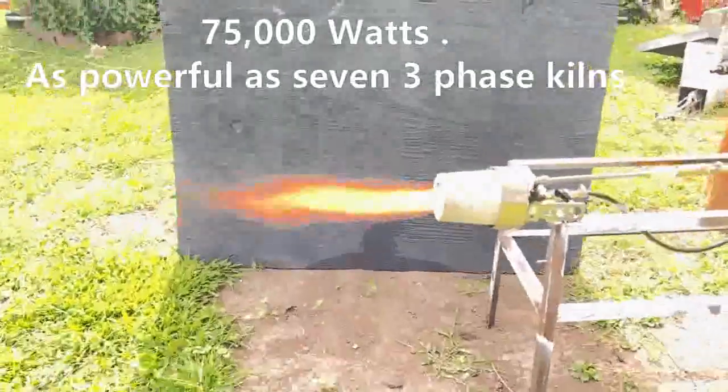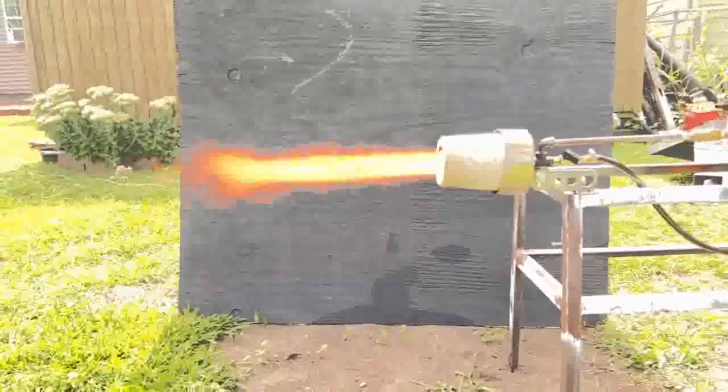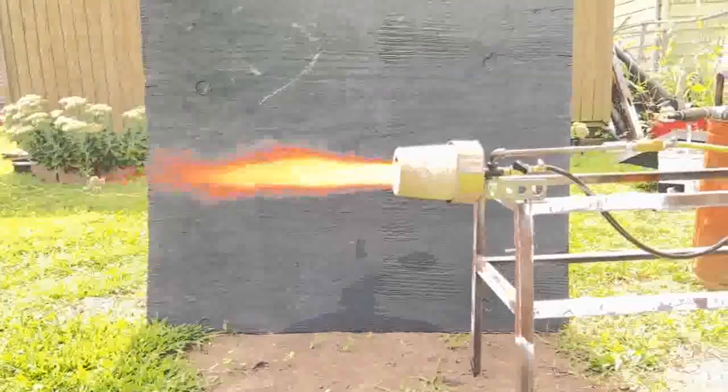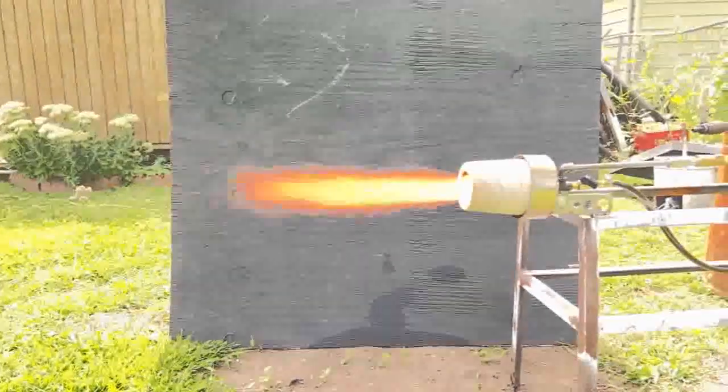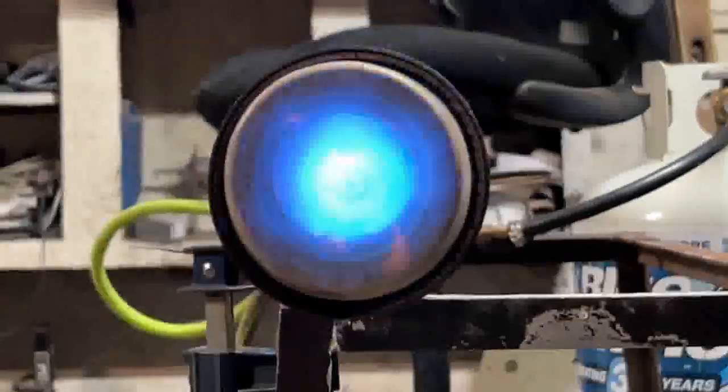What we're looking at right here is a 75 kilowatt burner, and I have never been able to run a single waste oil burner this small anywhere near that. Typically, 50 to 60 kilowatts is the most you're going to get.